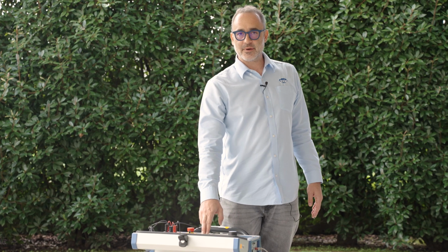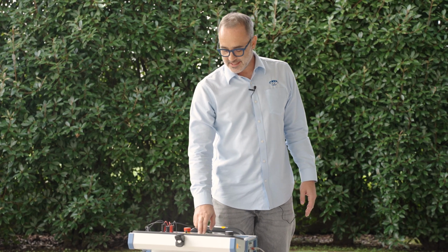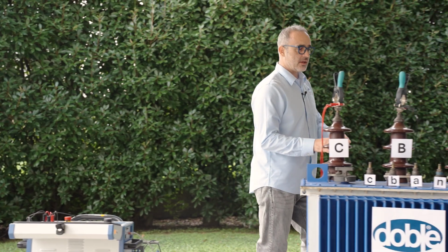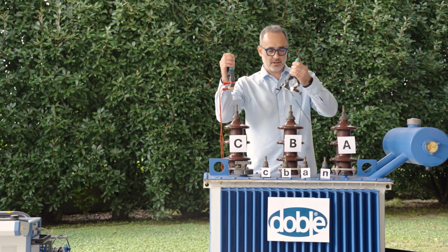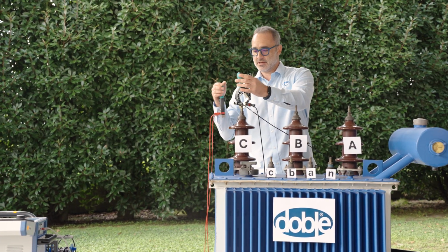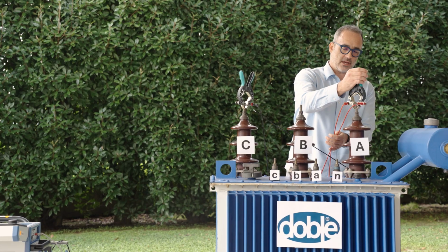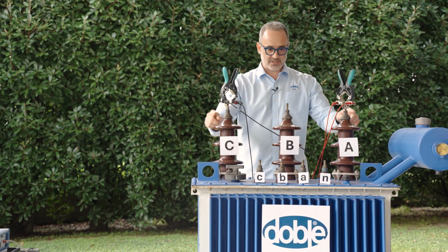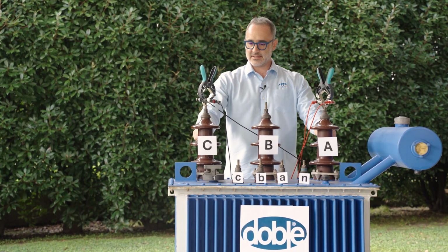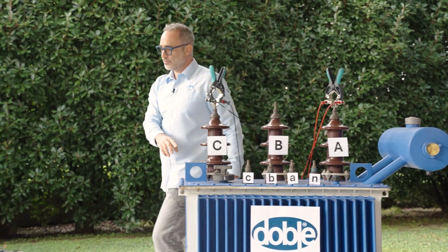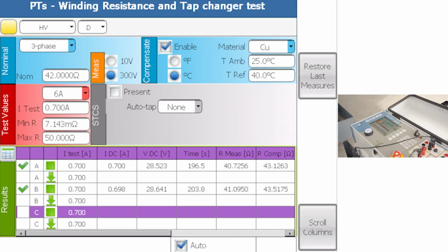All right, BC measured. Let's do CA. Once again, moving here, C, A. Now we are measuring the winding resistance between phases A and C. Let me now move to STS. Okay, I changed the connections to phase C, and now let's do, to be more accurate, the measurement of winding resistance between phases A and C.